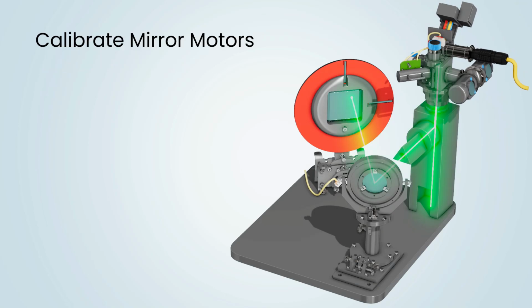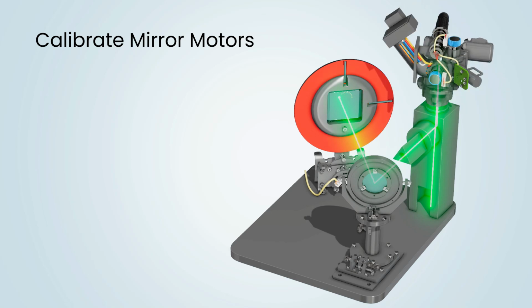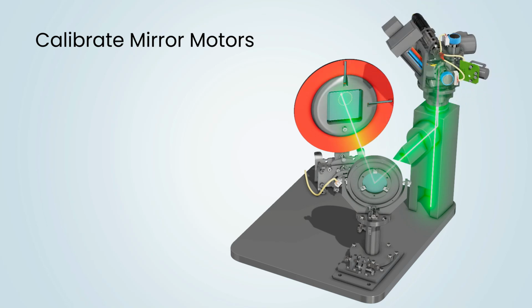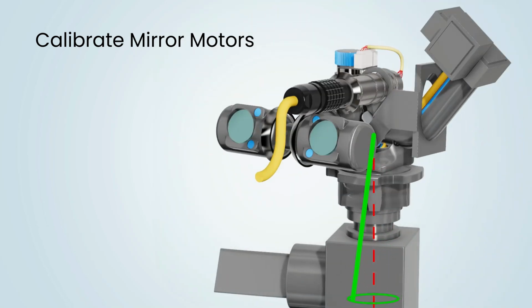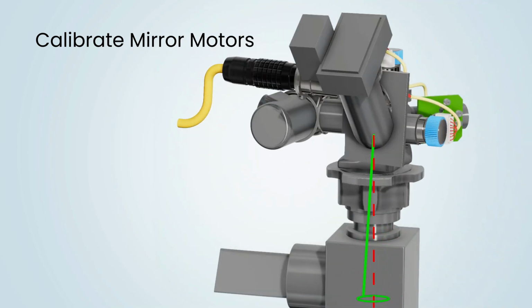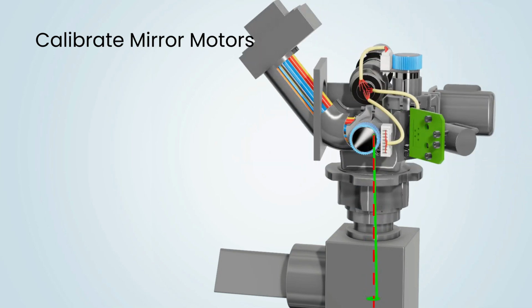Now we can calibrate the mirror motors so the beam will hit the target center when the assembly is rotated on the target jig and the drift of the beam remains centered and within a 10 mm diameter around the target center. By adjusting the motor knobs, we will align the laser beam with the axis of rotation of the assembly as it is rotated on the target fixture. This axis is effectively the zero direction we calibrate to.